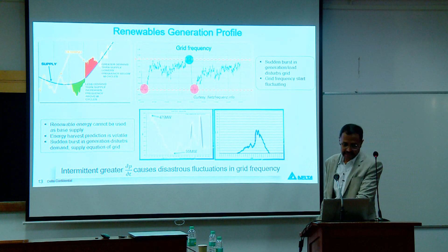Another challenge is that you have these renewable plants, which normally generate at 690 volt, and we are going up to 1000 volts now. We step it up to 33 kV till we send it to the receiving station, from where it is connected to the grid. You have a distance of around 50 to 200 kilometers, and as our profile is not fixed, this line behaves very badly for the grid, because it can become capacitive and it can become inductive too. Under no load conditions, it is completely capacitive. So the 400 kilovolt voltage on this side can fluctuate as high as 480 kilovolt. At that point, they have to disconnect these plants. Otherwise, this is a nuisance.